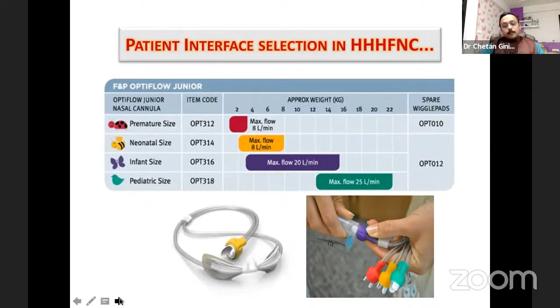It is all mentioned on the back of the nasal cannula packet. So what do we do? We set the flow rate. If the weight is less than 10 kg, you can set it at 2 liters per kg per minute. If the weight is more than 10 kg, set the flow rate at 2 liters per kg per minute for the first 10 kg and 0.5 liters per kg per minute for each kg above 10 kg. So start at a lower flow rate, let the child become acclimatized, and slowly increase the flow rate within the next 5 to 10 minutes.